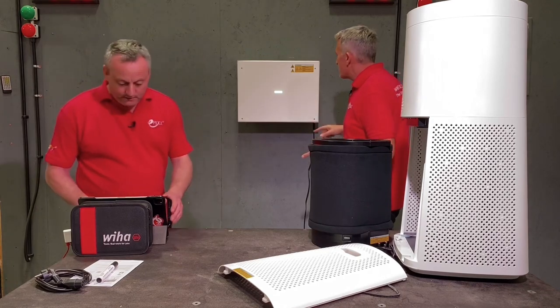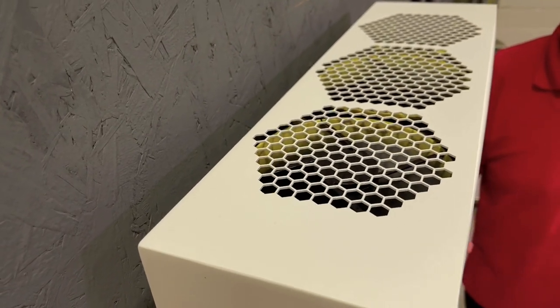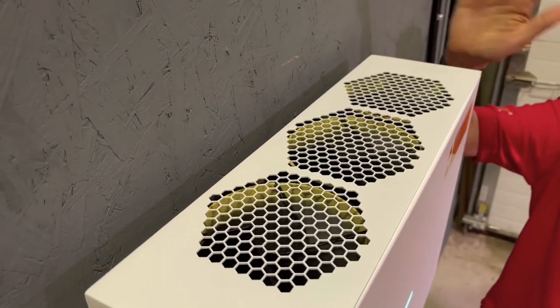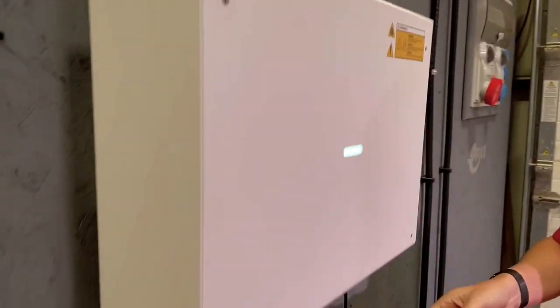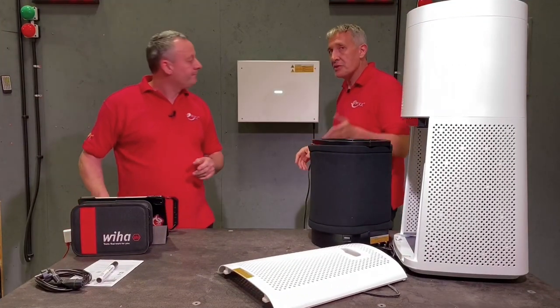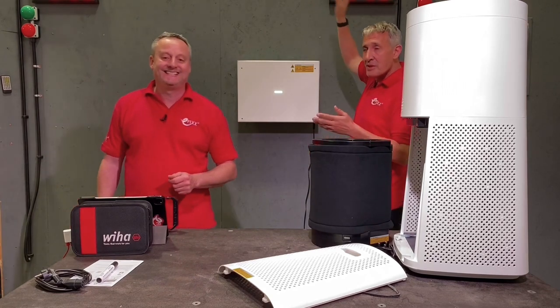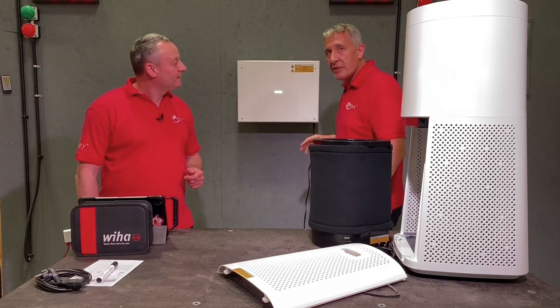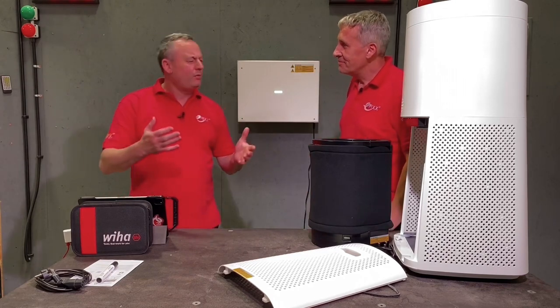Perhaps just have a look on top, Gary — see how clever the baffle design is in this unit. On the air disinfection units we looked at before, you could see the UV light if you were side-on to the unit, and with this one, you can't see anything. Also remember, with this unit you could mount it on the ceiling as well — it's not just a wall-mounted unit. The instructions say it should be half a metre from the top of a ceiling or half a metre from the side of an adjacent wall. Between the two units, we're talking about covering floors of between 20 and 30 metres squared.